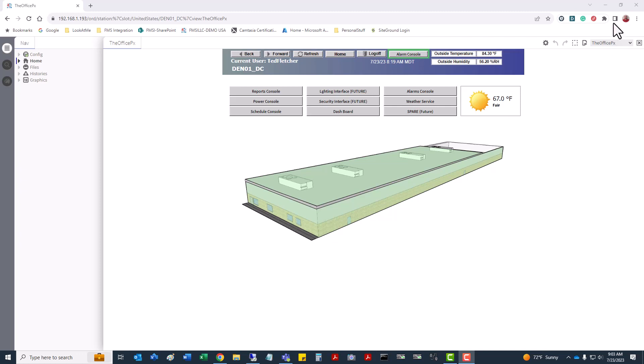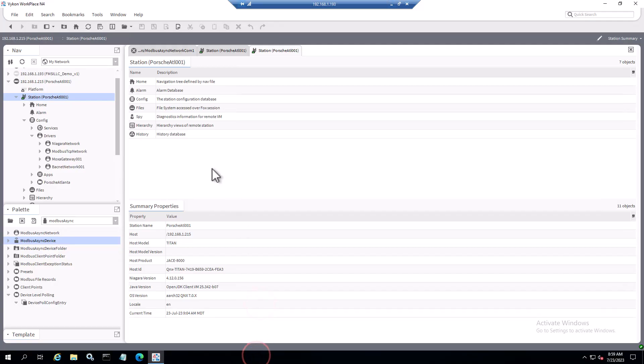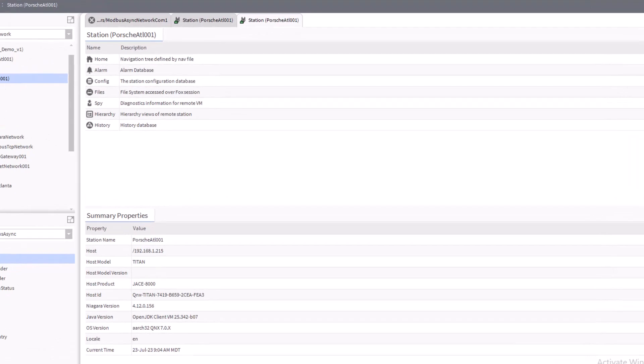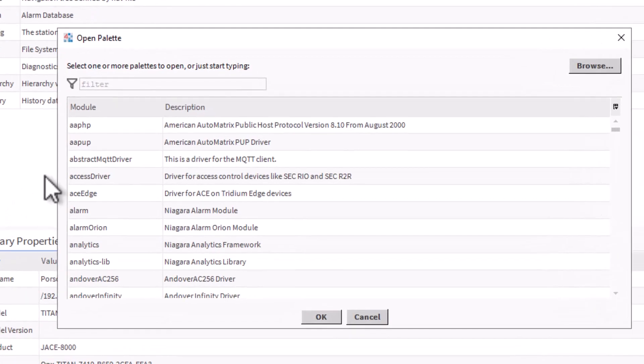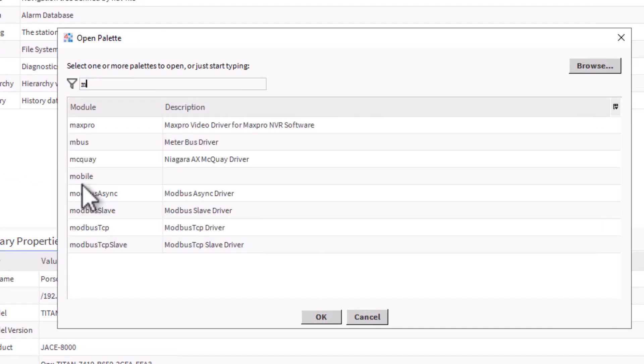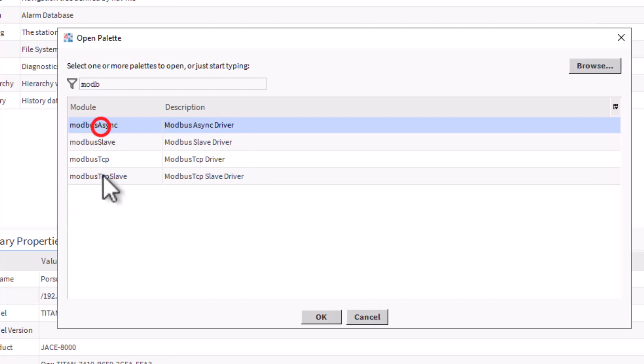First thing you need to do is have Workbench opened and log into the particular station that you're working with. When you come down and look at drivers, expand that out and you can see the networks currently set up. You want to have the Modbus async network selected. If you don't already have this in your palette, click on your open palette folder, type in Modbus, and it's that first option you see: Modbus async.